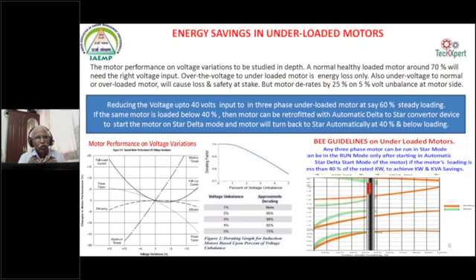At that band, if the motor is loaded more, the efficiency is also dropping. If the motor is loaded correctly, around 60 to 80%, the efficiency is almost sustained at 100%. You can see the motor performance under low voltage variations at the right bottom of this PowerPoint. We can see the power factor and the full load current variations are very much more compared to the efficiency, at -15 and +15 for a given rated normal loading of the motor. If the loading of the motor is only around 60%, let us say.